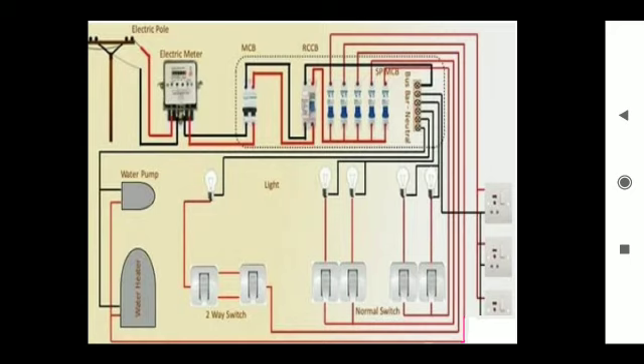There are 5 sub-circuits in the bus bar. That means there are 5 MCBs, and according to IE rules, 800 watt and 10 points are connected in a single sub-circuit. We can see there are several lighting loads, water pumps, water heaters and electrical sockets connected with this house wiring.